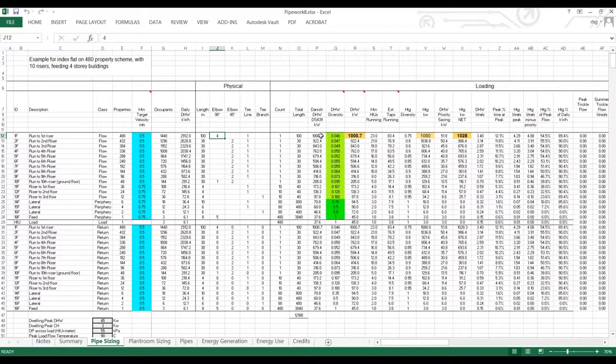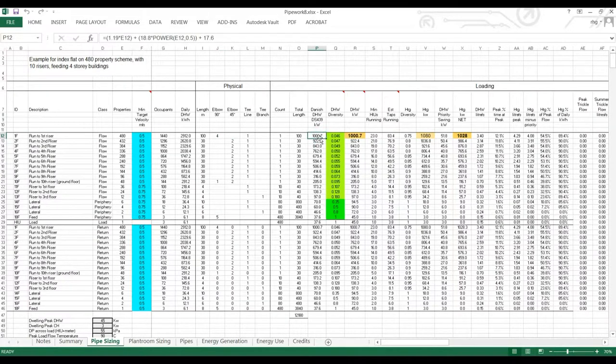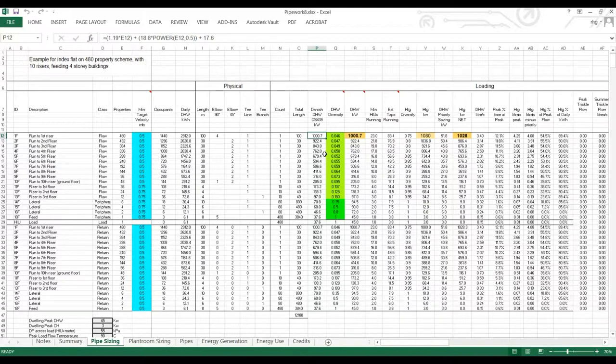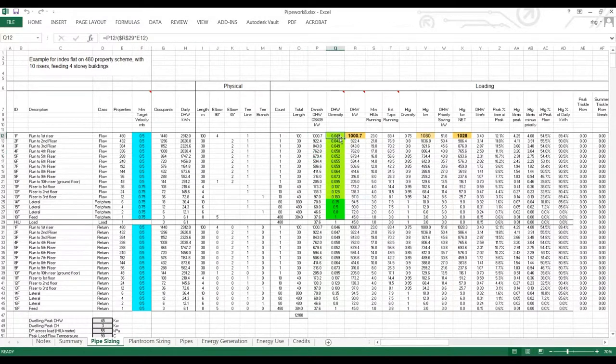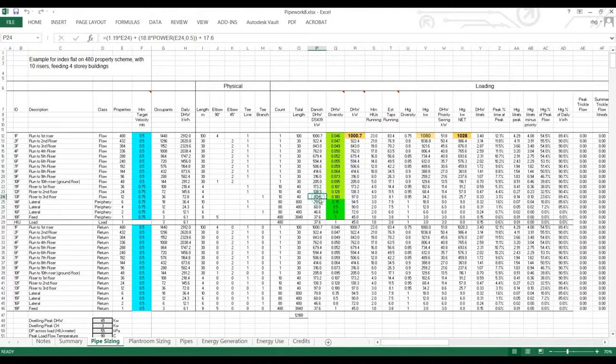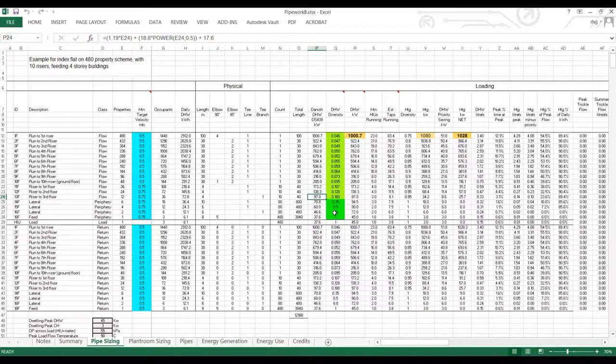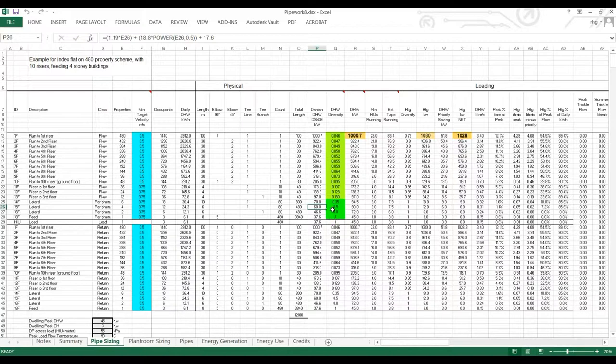We have the Danish diversity calculation. So this is the equation up here. And the selected hot water diversity. So most of these we've gone with the Danish. Down to the very low end where we've put the diversity slightly higher, as it's been shown in some recent studies it can be.